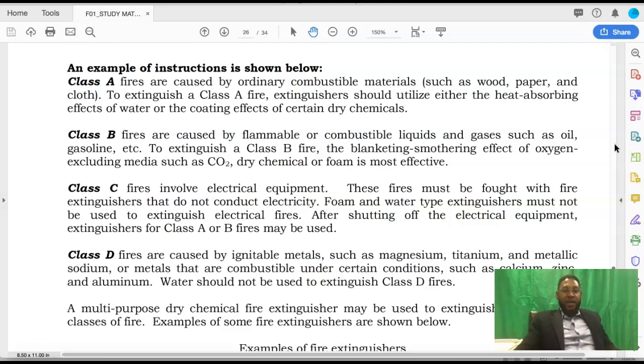Class A fires we know to be ordinary combustibles. Ordinary combustibles could be categorized as wood, paper, cloth. Alright, so that is the ordinary combustible kind of fire. Mattresses, boxes. So to extinguish a Class A fire, extinguishers should utilize either the heat absorbing effect of water or the coating effect of certain dry chemicals.